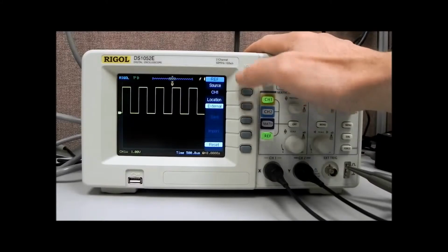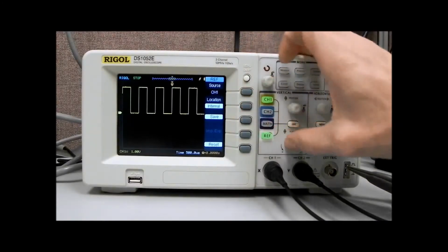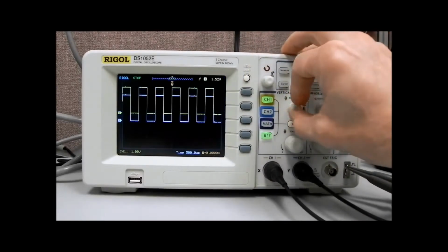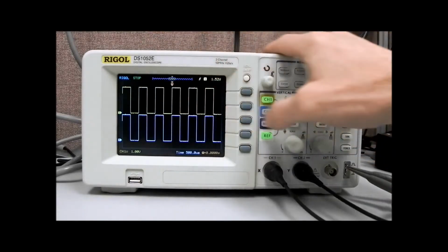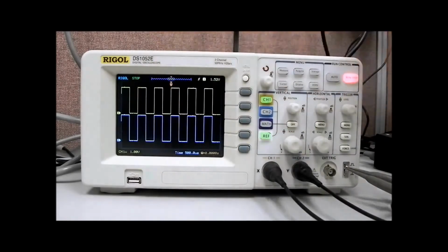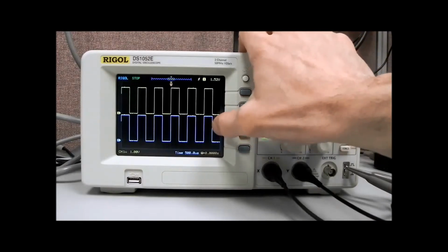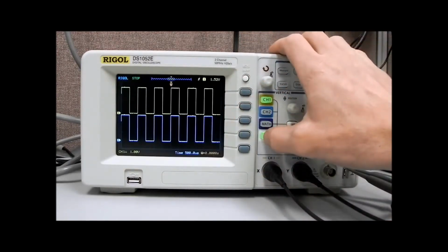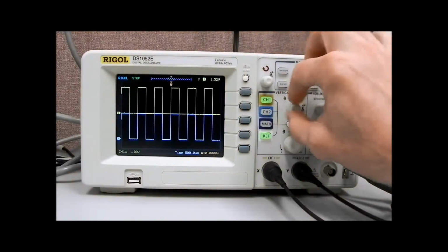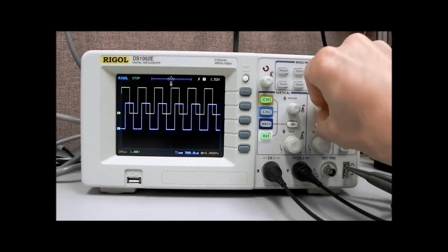Now let's do external. Actually, let's do internal, and let's hit save, and now you'll see that the reference waveform, and we'll just have to move it out of the way, the reference waveform is exactly like the waveform that we've captured here. You'll notice that it's also stopped. So it's taken a capture of a particular slice in time of that waveform as it's coming into the input, and it's replicated that here. It can be manipulated just like the regular waveform, in that we can raise it and lower it, and we can also shift it in time.